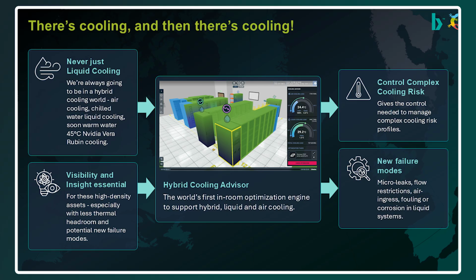100%, and the different phases of the life cycle for the customer, because they're not switching them on full bore on day one. You need ramp up time, you need to adjust your cooling setup to deal with the end state, but they may not get there for 6-7 months from deployment. So you need a system that can adapt to those changing design requirements and roll-up stages.